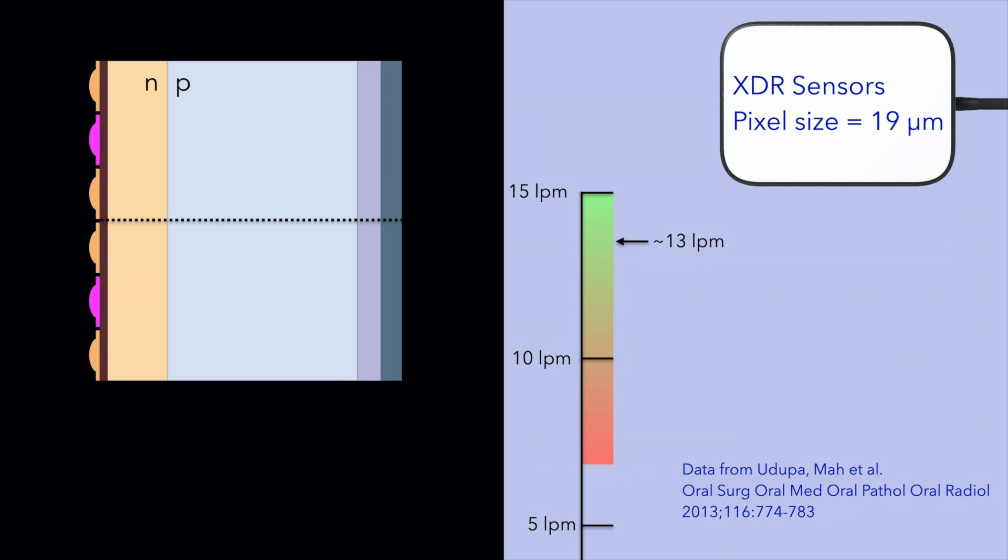On a practical basis, however, the resolution of the image is much lower than 26 line pairs per millimeter. This depends on the X-ray tube that you use, the size of the focal spot, scatter radiation from the patient, electronic noise within the detector, and so many other elements.